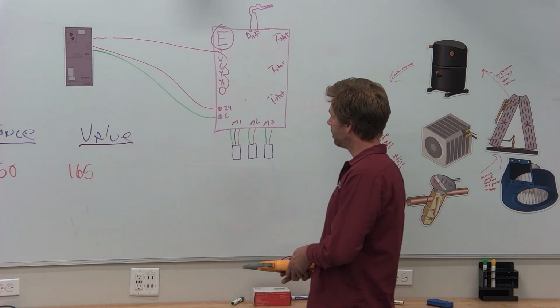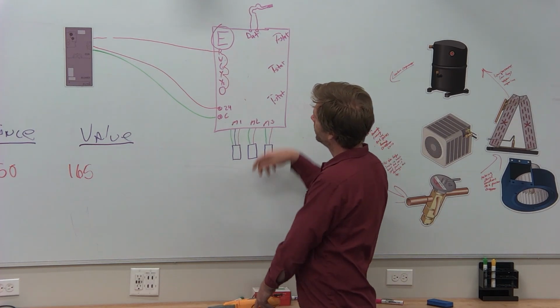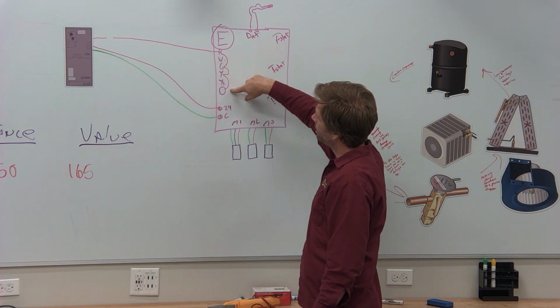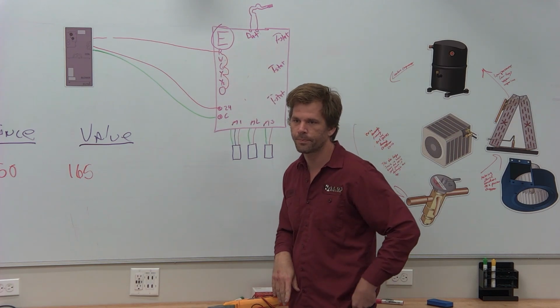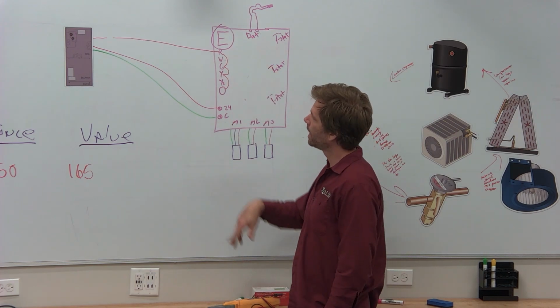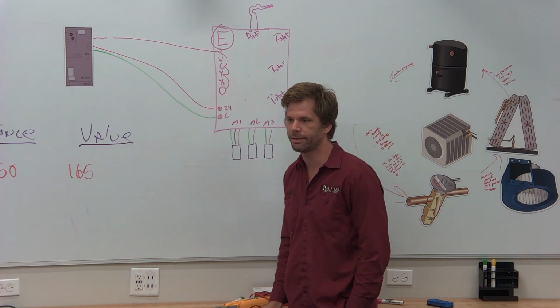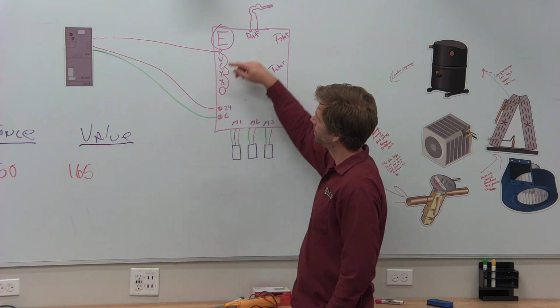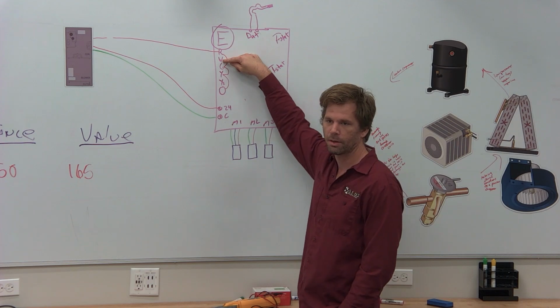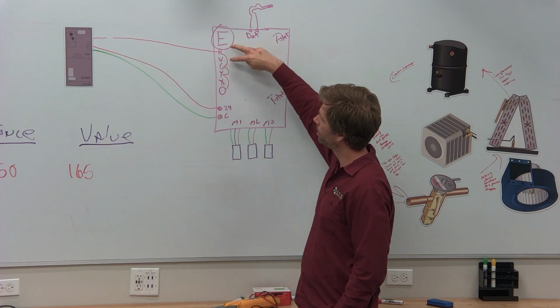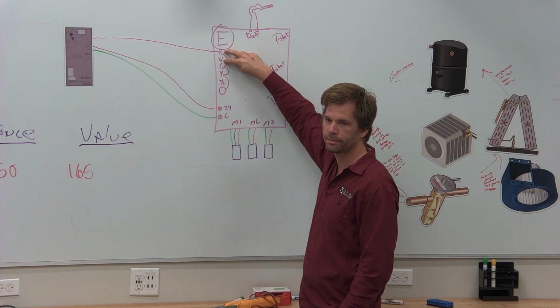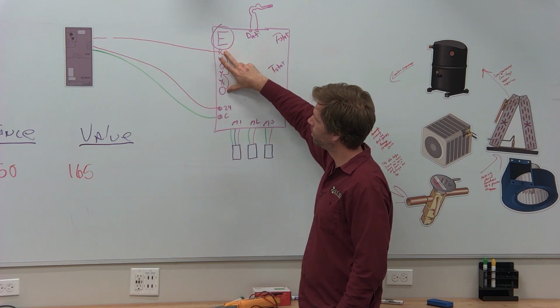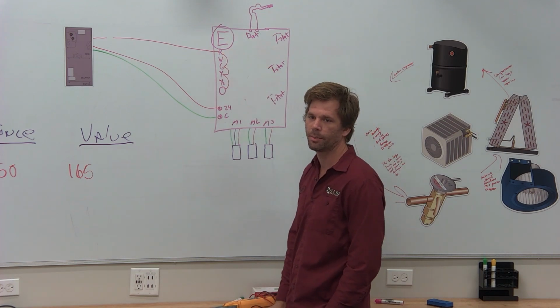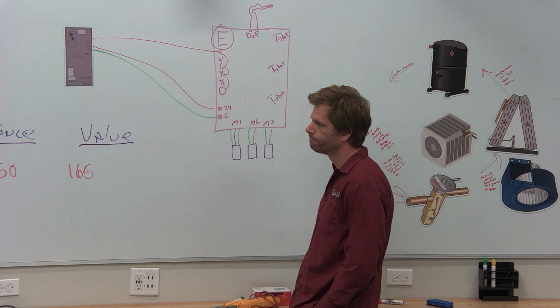So on here, our meter is showing us that there's 0 potential difference between R, G, Y, and O. We're calling cool mode. Or we have 0 power on R and it's telling us 0. So to confirm that, check between R and W. We know we're not calling W in cool mode. R and W should have 24 volts. R and O, 0. Okay, I know I'm calling my reversing valve. Great.